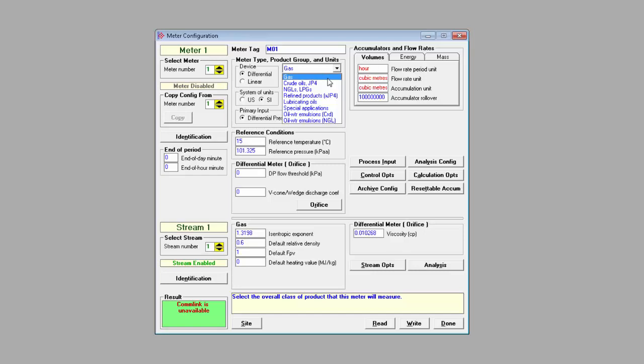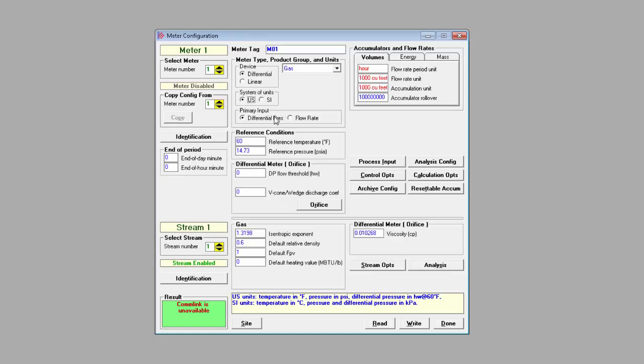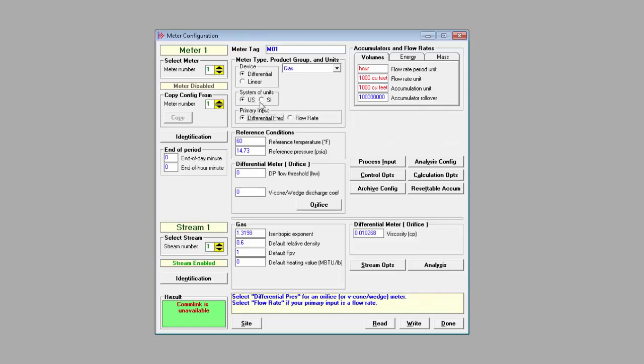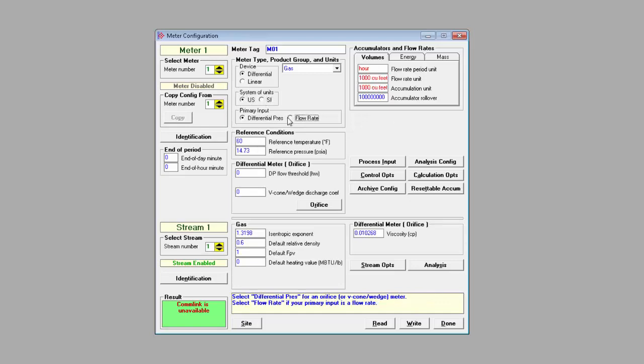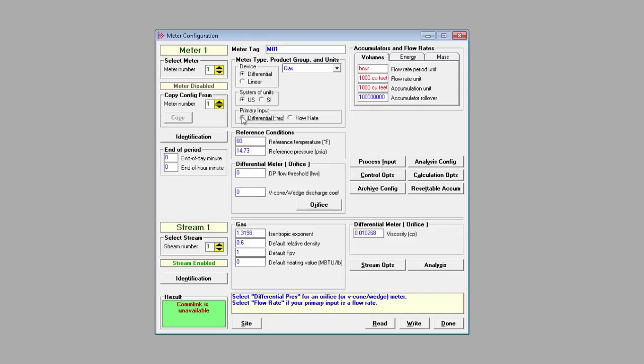Next, you will choose the product group. For most applications, either gas, crude oils, or NGLs or LPGs will be the typical choices. But for special applications, there are other options as well. Next, the system of units you want to use, US or metric. And finally, the primary input: Pulse count or pulse frequency for linear meters, and differential pressure or flow rate for differential meters. The parameters you choose in this section will determine what other parameters EAFC Manager will display. And you'll notice that as I make changes here, the displayed parameters also change. Only the parameters that pertain to your meter type and instrumentation and its primary output will be displayed.